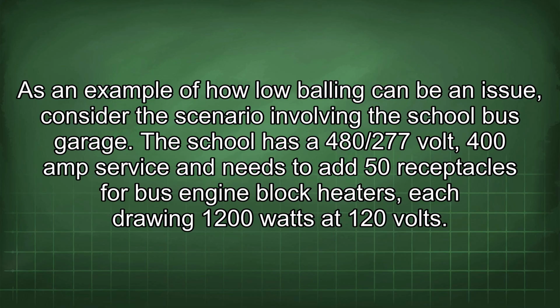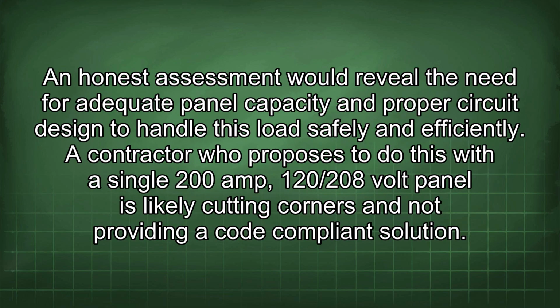The school has a 480/277 volt, 400 amp service and needs to add 50 receptacles for bus engine block heaters, each drawing 1200 watts at 120 volts. An honest assessment would reveal the need for adequate panel capacity and proper circuit design to handle this load safely and efficiently.